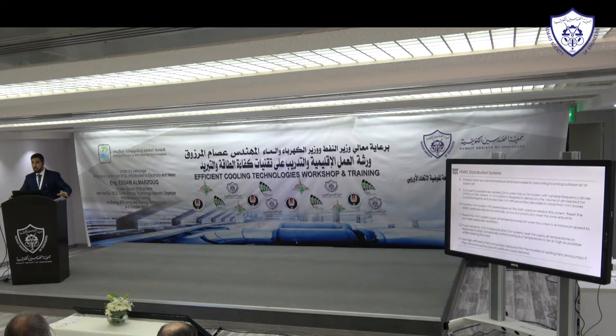Convert CAV (constant air volume) systems to VAV (variable air volume) by adding VFDs to air handling units — similar to what we discussed for pumps. The amount of airflow to a room shouldn't always be the same; it should adjust based on occupancy, indoor loads, and outdoor loads. Installing a VFD on the air handling unit reduces consumption significantly, and because consumption is related to fan speed by the cube, 20% reduction in fan speed means 50% reduction in power.